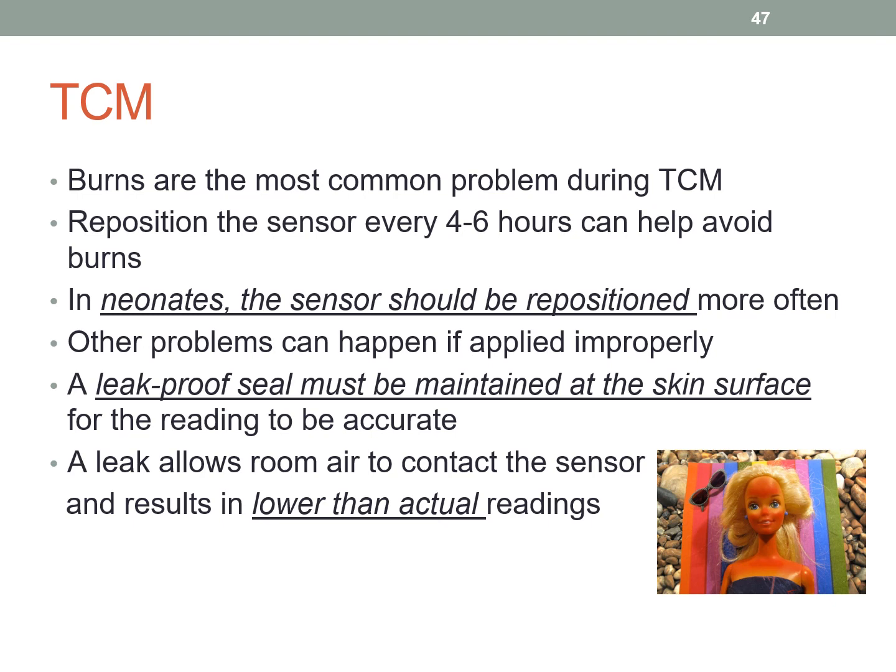You can also get a leak, meaning an air leak, so you have to make sure you have a good seal on them. A leak allows room air to contact the sensor, and that would result in lower than actual readings. Make sure you know that, because I think that might be a test question.